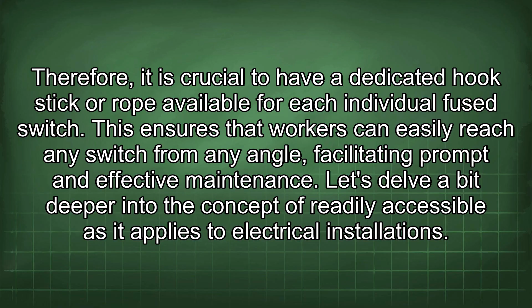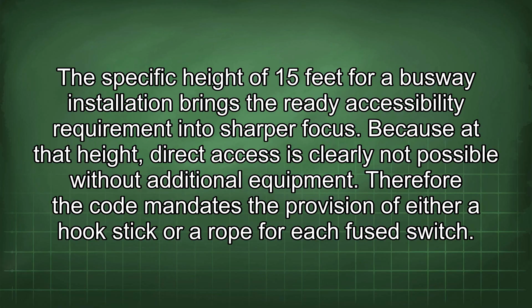Let's delve a bit deeper into the concept of readily accessible as it applies to electrical installations. Readily accessible, as defined by the NEC, means capable of being reached quickly for operation, renewal, or inspections, without requiring those to whom ready access is requisite to climb over or remove obstacles or to resort to portable ladders, and so forth. The specific height of 15 feet for a busway installation brings the ready accessibility requirement into sharper focus, because at that height, direct access is clearly not possible without additional equipment. Therefore, the code mandates the provision of either a hook stick or a rope for each fuse switch.